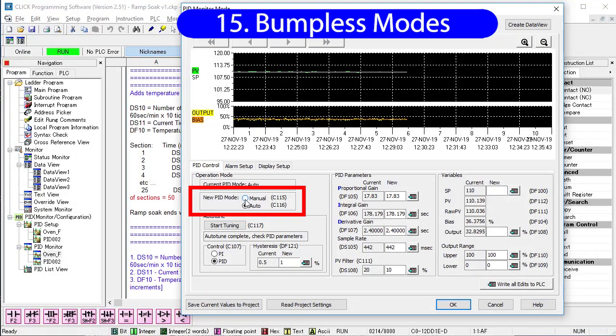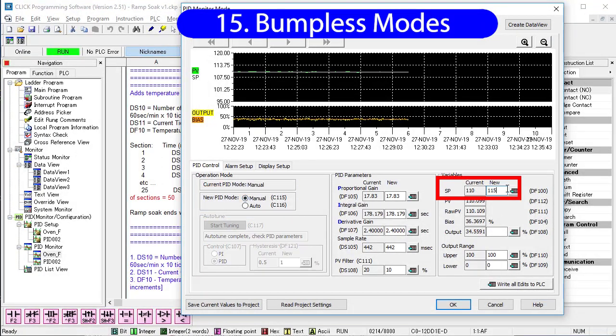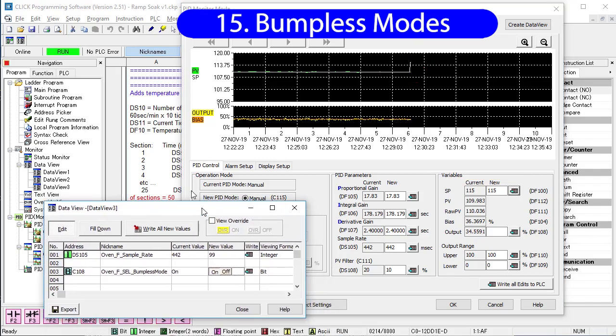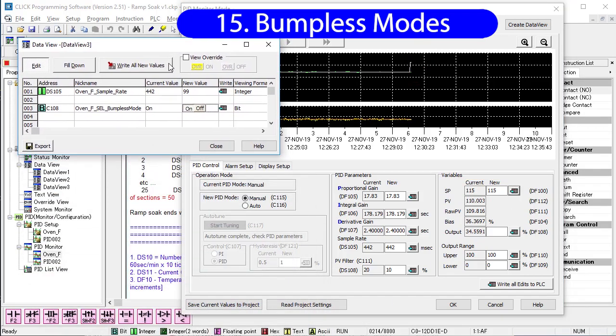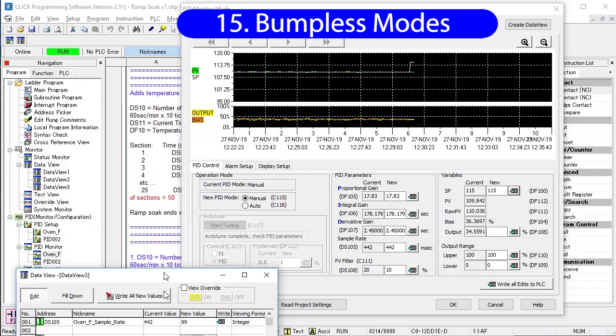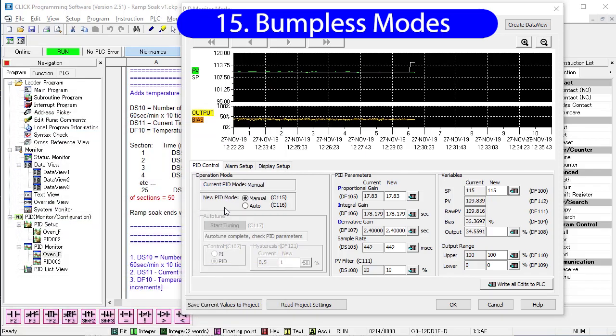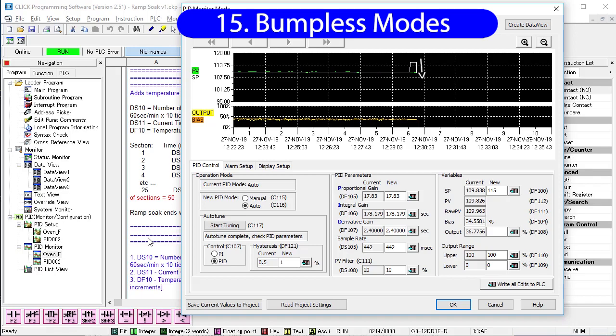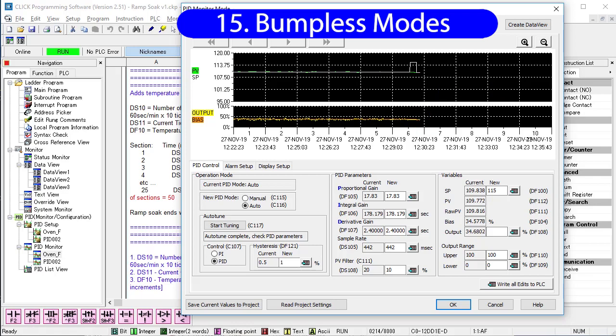For example, I'll switch back to manual mode and make sure there is a good separation between a process variable and a set point. I'll bring up a data view and switch to bumpless mode. Now when we enter auto mode, the set point was automatically forced to be the same level as the process variable so PID wouldn't see any need to make a large change in the output. Now we can gradually raise the set point in a controlled manner to keep the system from creating a hazardous situation.